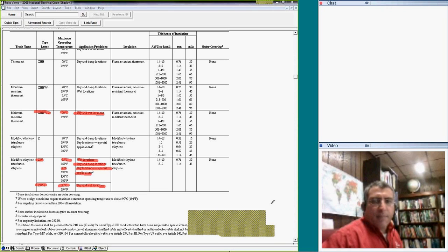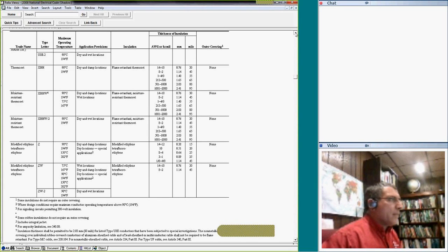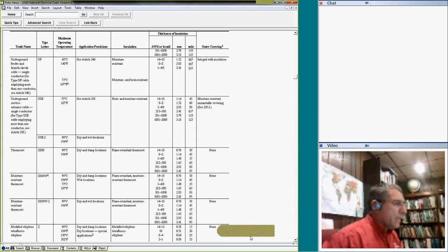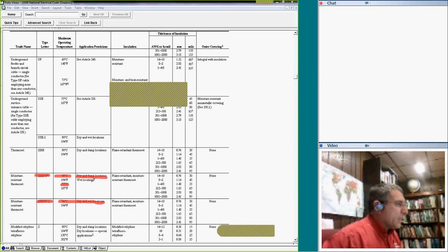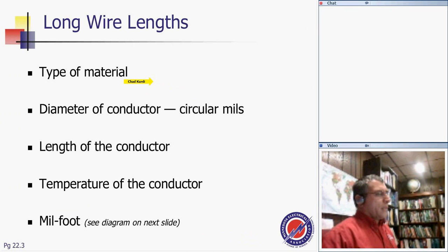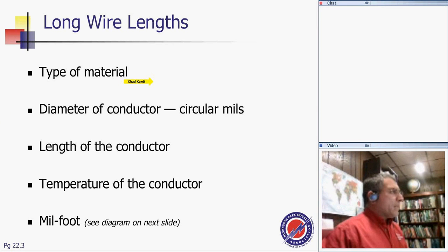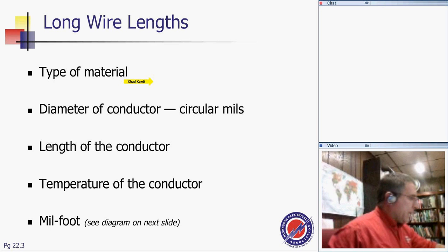Questions, guys? Any comments about how to use this table? Especially this insulation here, I always trick you with that because it's always rated for dry location 90 degrees, and then I get you with this insulation, XHHW. It's 90 only if it's dry and damp, and if it's wet, it's actually 75. They trick you on the journeyman exam with that particular one. Okay, that's basically how to use the table and the ratings.